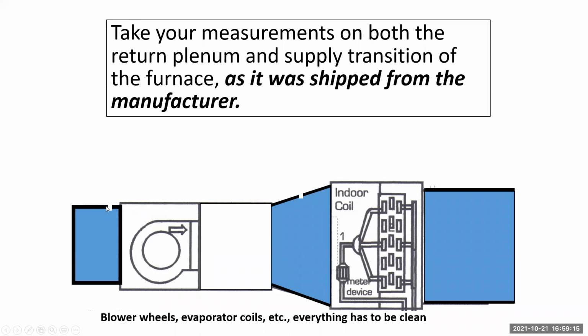After the filter, before the blower, after the furnace, before the evaporator. I'm going to repeat that because you're going to see it here in about 10 minutes when you take your test. Well, actually, after Rob's done. Sorry, Rob, I forgot you're next. But again, after the filter, before the blower, after the furnace, before the evaporator is where static's taken. We may, during talks, have you pull pressures from other areas, but that is where we're starting.